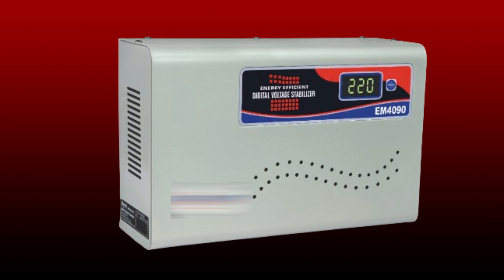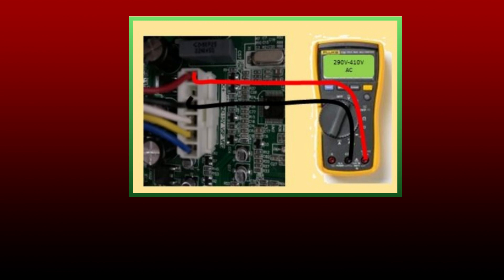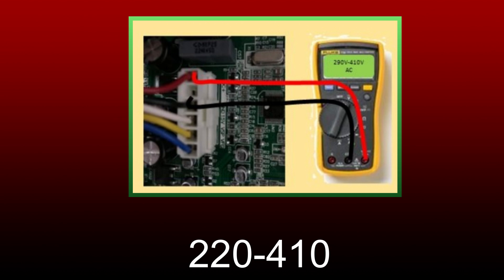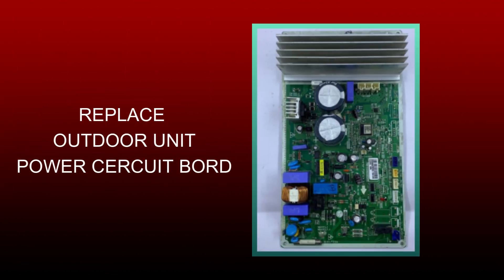If the voltage of your house is fine and still this error is coming, there could be another reason. Turn off the main switch, open the PCB of the outdoor unit, then turn on the AC and check the voltage at the connector of the fan motor. If the voltage is too low or too high from 220 volts to 410 volts, then your outdoor PCB is faulty and you need to replace it. This error will be completely resolved after replacing the PCB of the outdoor unit.